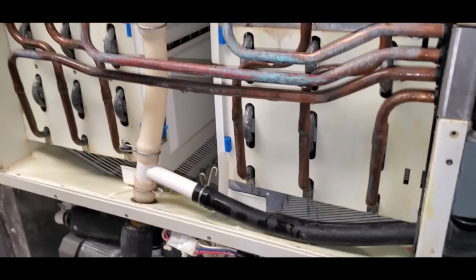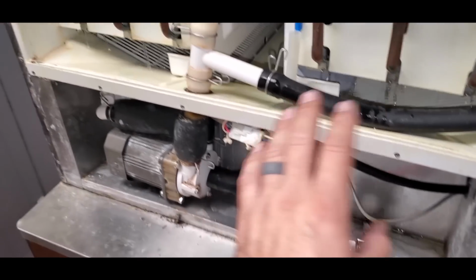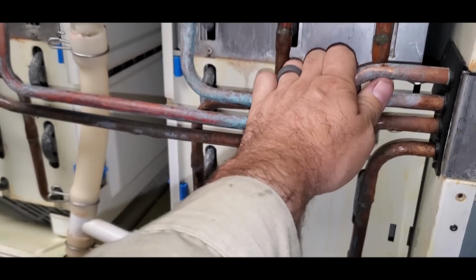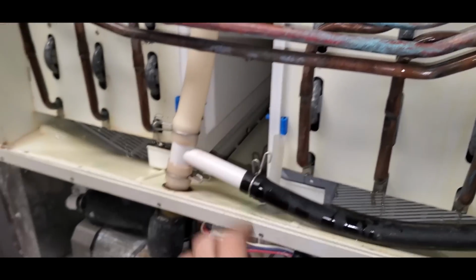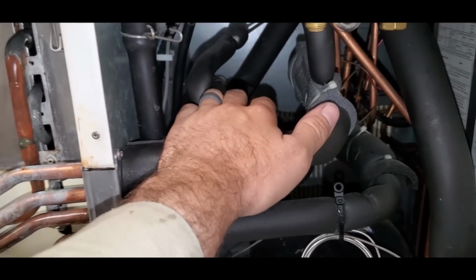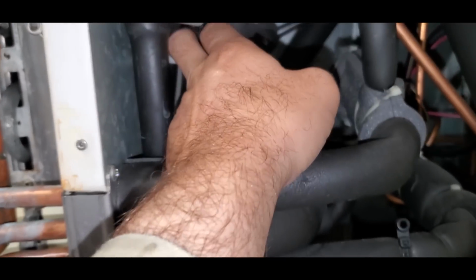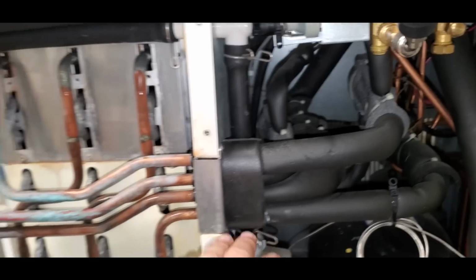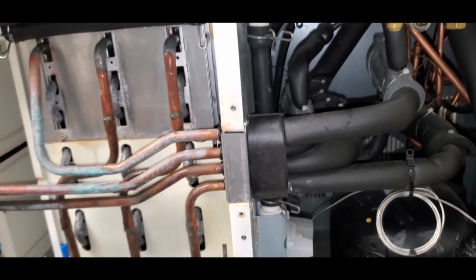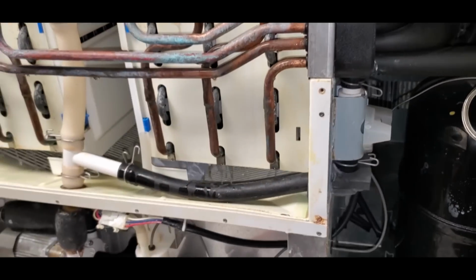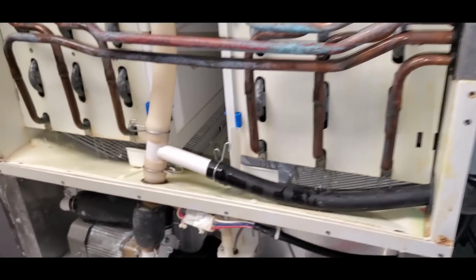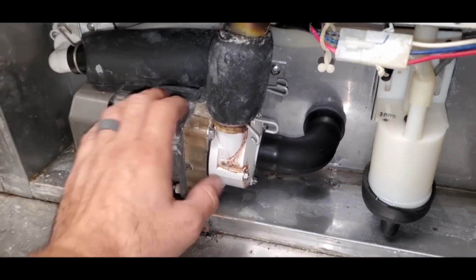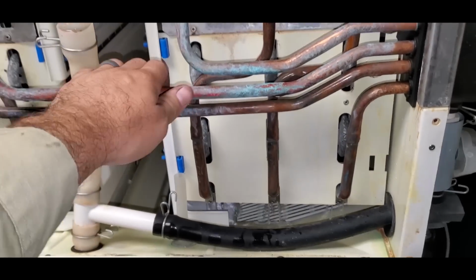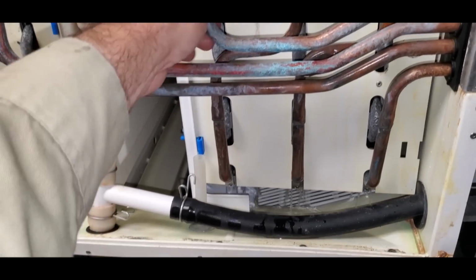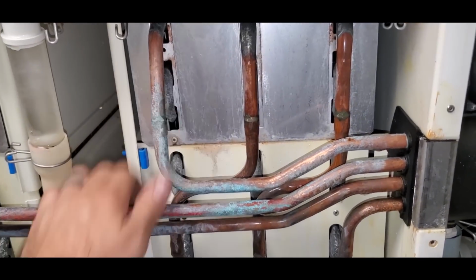The unit is currently still going through its harvest, and again, we've got warm refrigerant lines coming into the evaporator. The moment that the thermistor, which is tucked back in here, it's this little wire right here, the moment that the thermistor senses a certain temperature, I can't remember that number off the top of my head, and then when the water pump turns on, that's the moment that the machine, actually no, it takes one more second here. We'll know when the hot gas valves turn off, then we'll know we're in defrost.